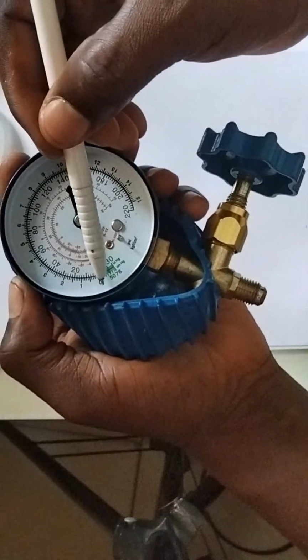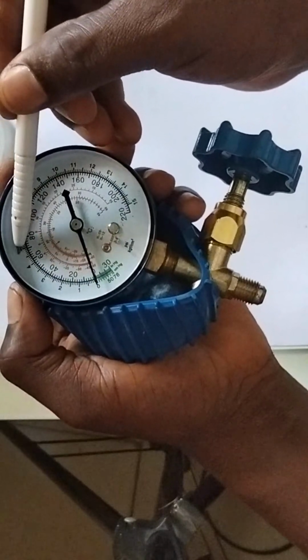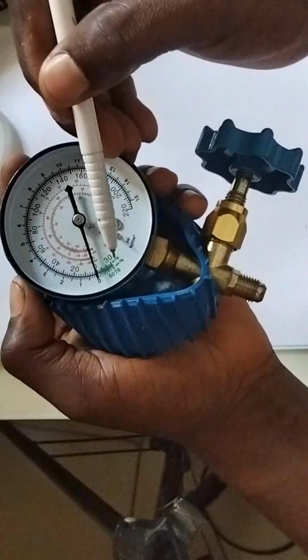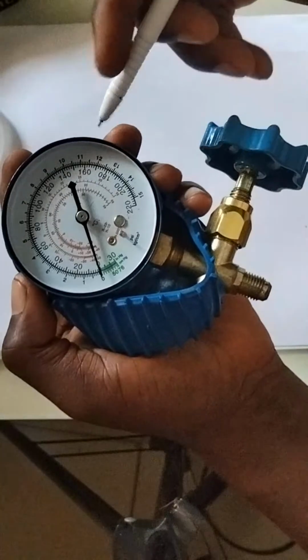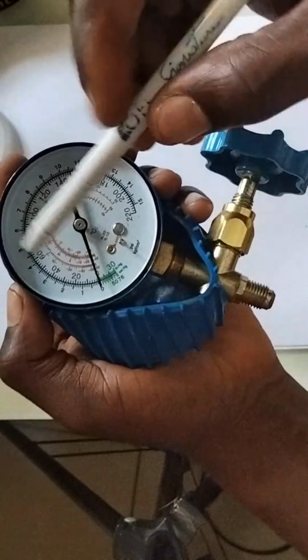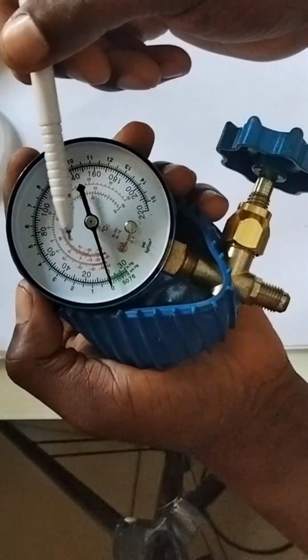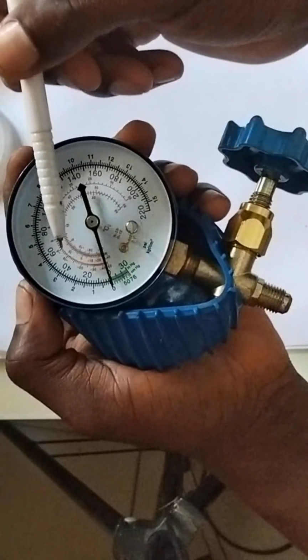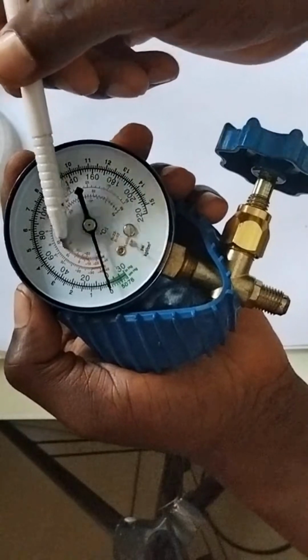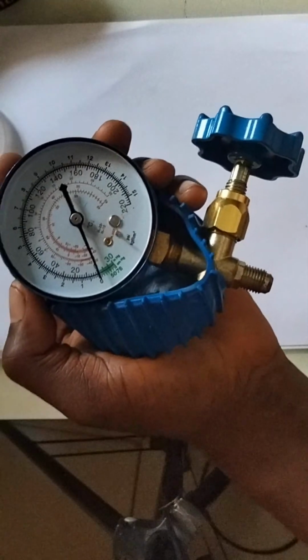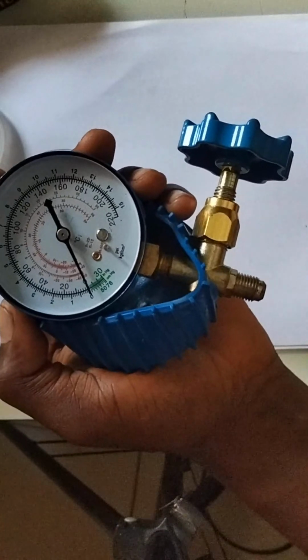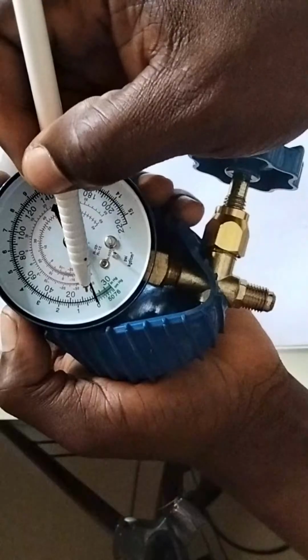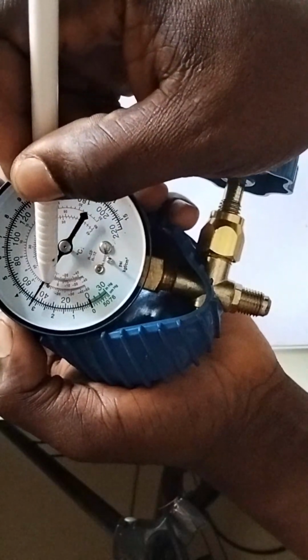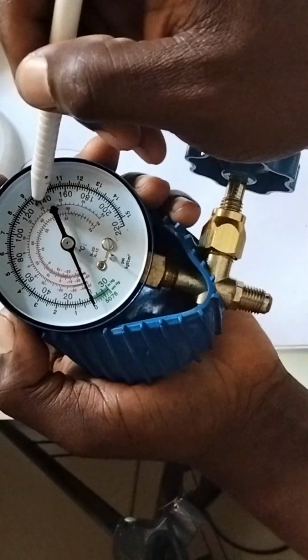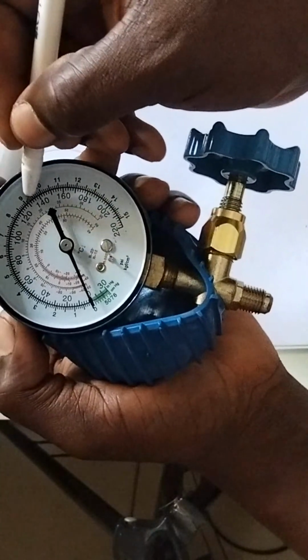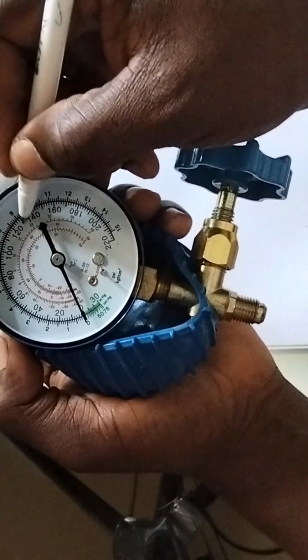Okay, let's continue. The first calibration up here entails the kg, which is the kilograms of refrigerant you are using at a particular time. But the PSI and temperature readings are for R502 and R22 here. For R410 refrigerant, the PSI is between 120 and 140 PSI. So if you are charging R410 refrigerant, this needle goes up to 140 PSI, or let me just say it stops at 130 PSI.